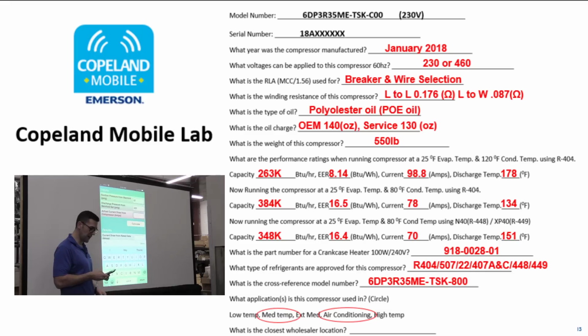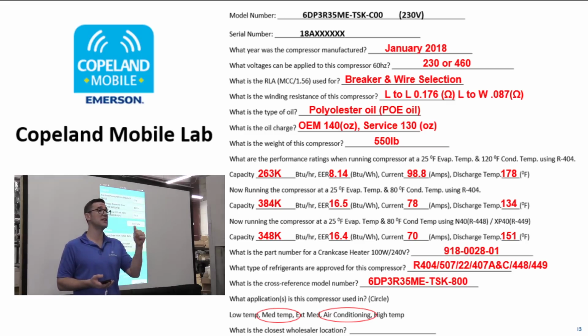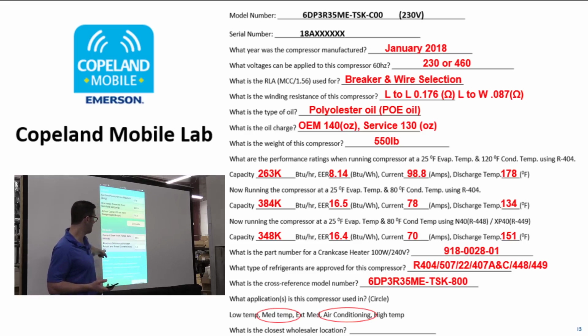And you'll have to check your amps. So I'm going to just say 90 amps. Calculate. Should be 88.6. We're 1.6 difference. Normal operation. So that compressor's running efficiently. You know the valves inside that compressor are working fine. You don't have to do any sort of valve test, we'll talk about that later. I know through this that this compressor is running totally fine.